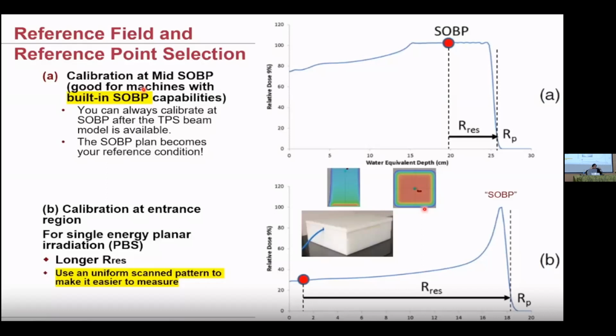When I do it with a Hitachi system, because whoever your manufacturer is, they have to do something to calibrate their monitor chambers in the head of their nozzle that's actually measuring the dose. And IBA does it different than Varian did it. It's different than Hitachi does it. So there's not a standard, right? Elekta and Varian pretty much do it exactly the same way that they've been doing it for the last like 30 years or so. So pretty straightforward. Here, there's not really one. In a Hitachi system, we do a liter cube.